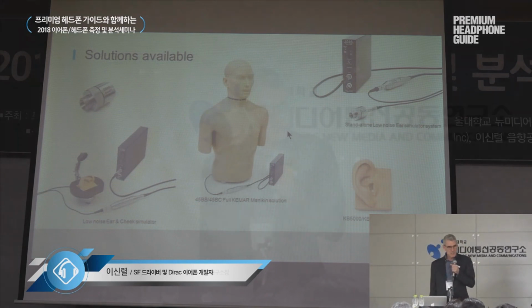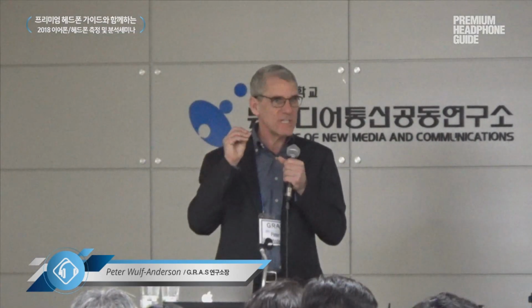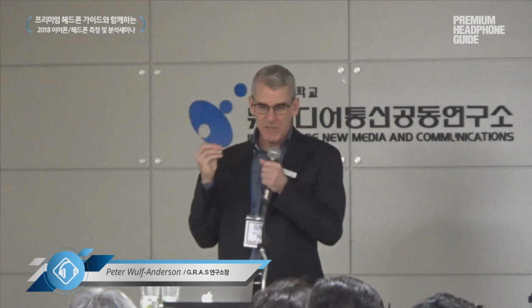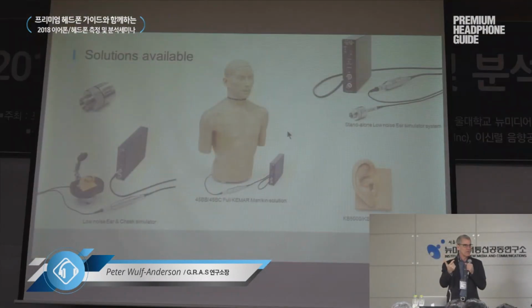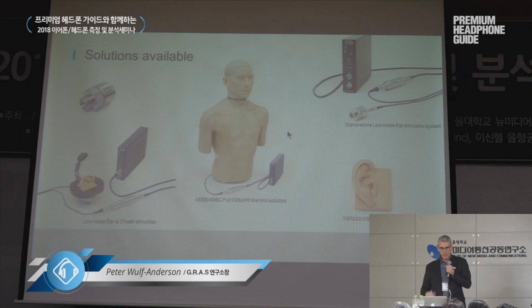So, as mentioned, we have always tried to keep all the solutions backwards compatible, and that means that the pinna, the low noise coupler, and the high resolution coupler can all be used in older setups because they are mechanically compatible. Therefore, it means that you don't have to buy a complete new solution. You can even say, I just need the coupler and I already have a KEMAR or another setup, and you can replace the coupler.